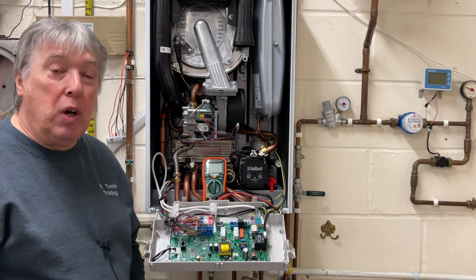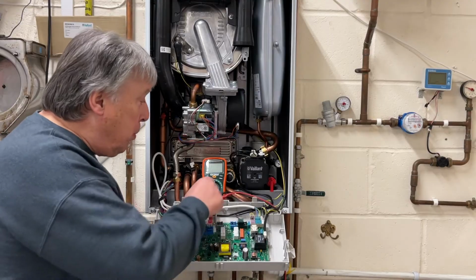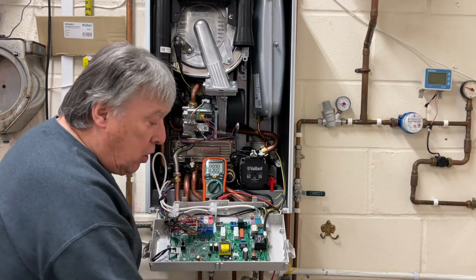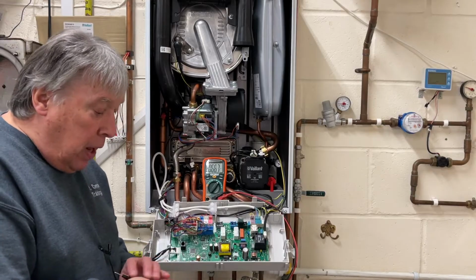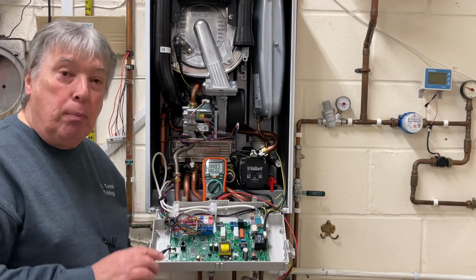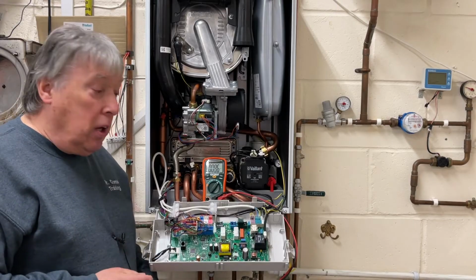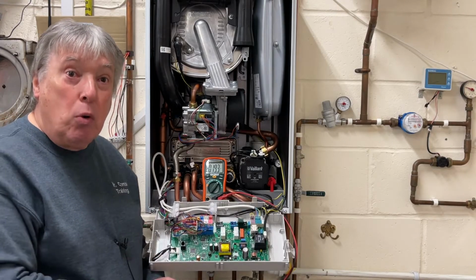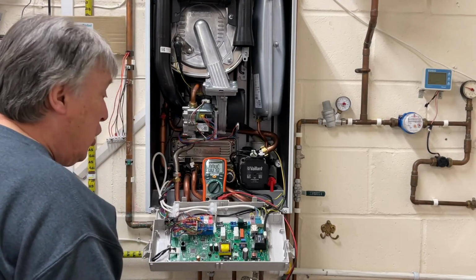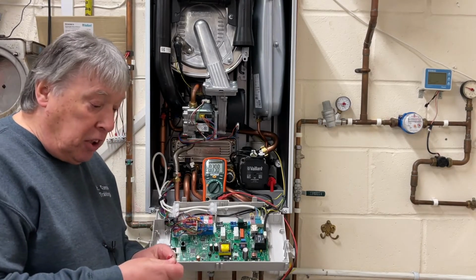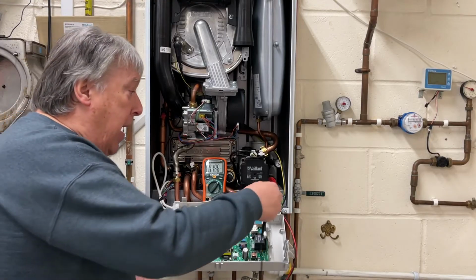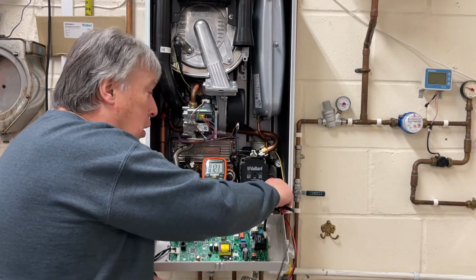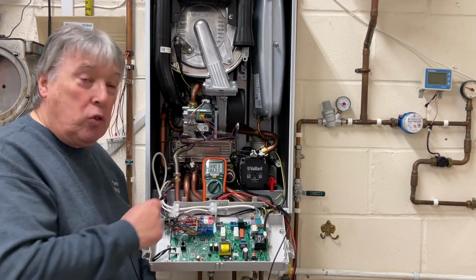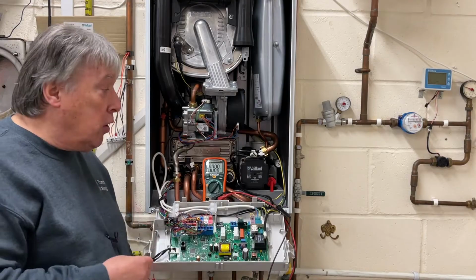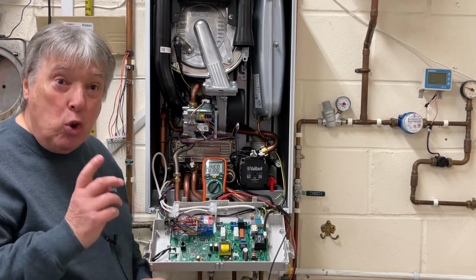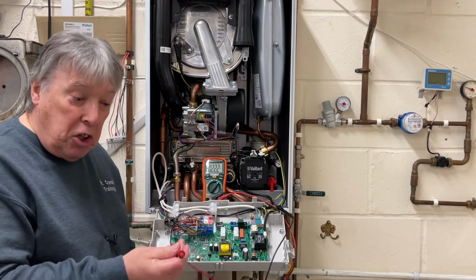Now I'll show you how to do it in DC. We put our selector switch into DC, and we've got our two leads. Because this particular part, the Aqua Sensor, has a black wire which is earth, we can use a crocodile clip attached to the probe and connect it where the yellow and green wires are. All the boilers have connections where the earth wire is connected - that's a good one, and then we can check much easier with just one lead.